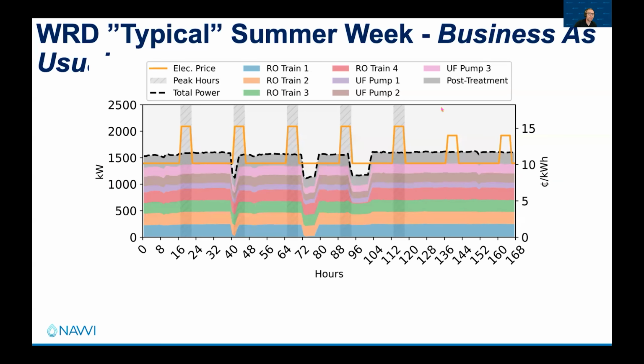Okay, so coming back to this stacked plot of power consumption for the typical summer week, this is business as usual. As you can see, they're operating constantly. They're not really doing any planned shutdowns to minimize costs during the peak hours. They are turning off some of the components, but not really in coordination with a grid price, maybe maintenance, we're not sure.